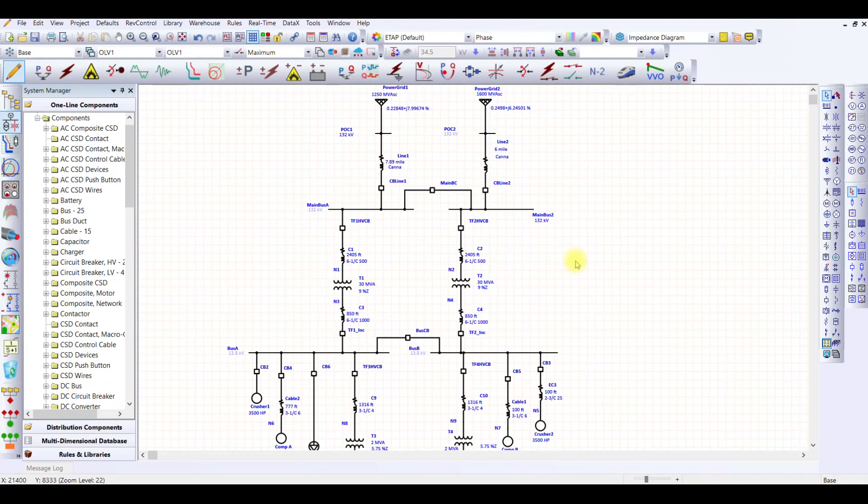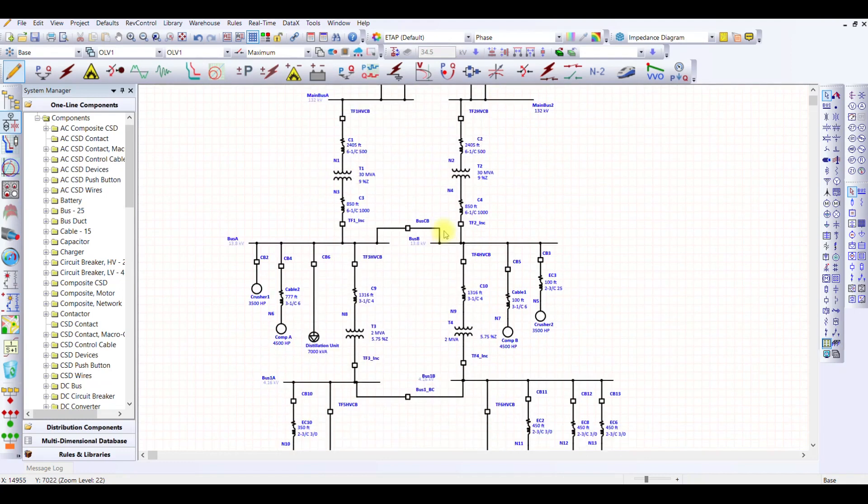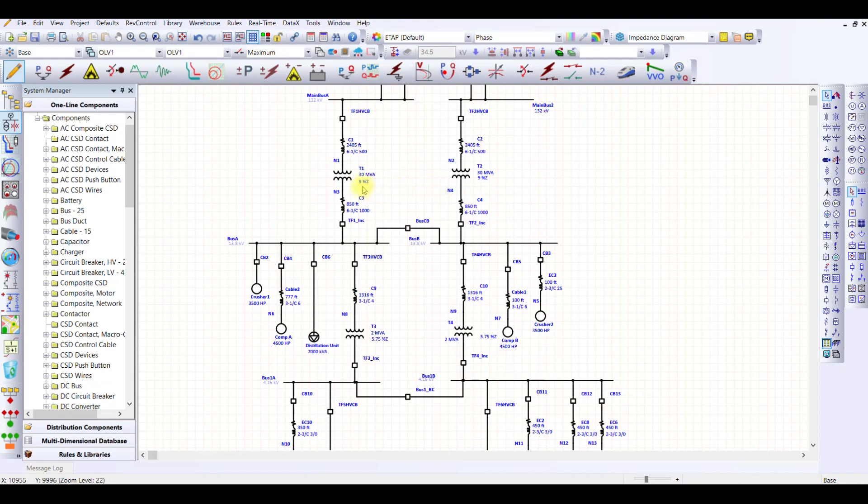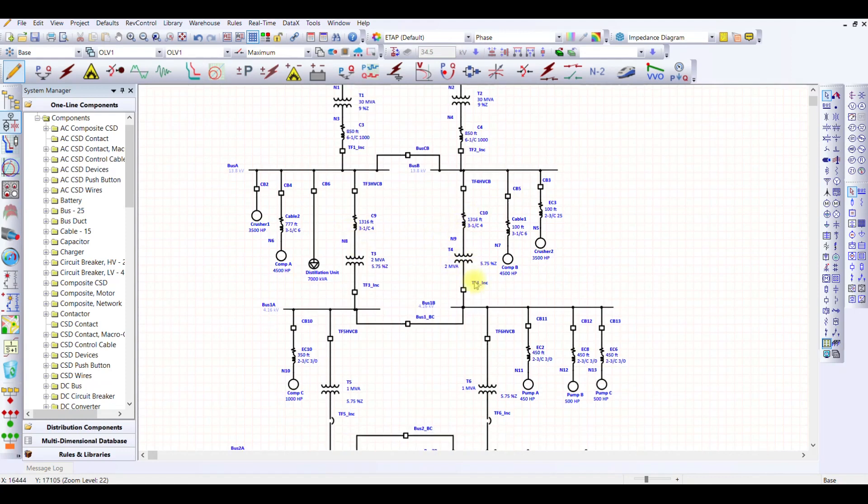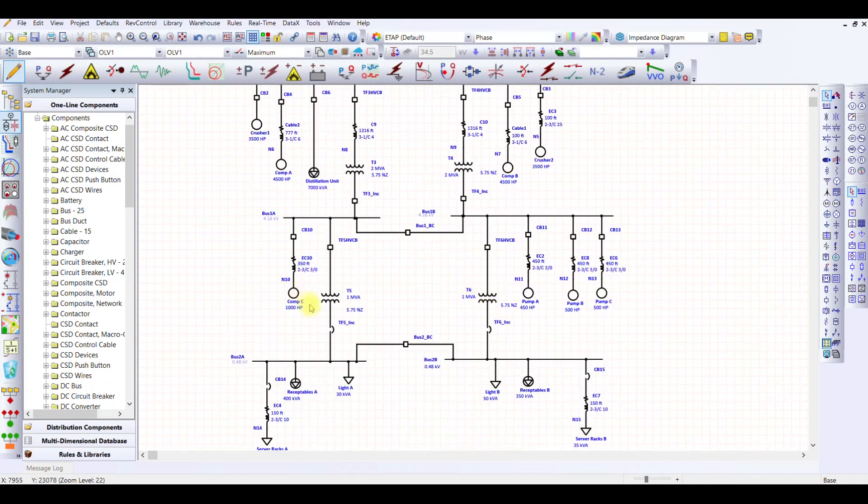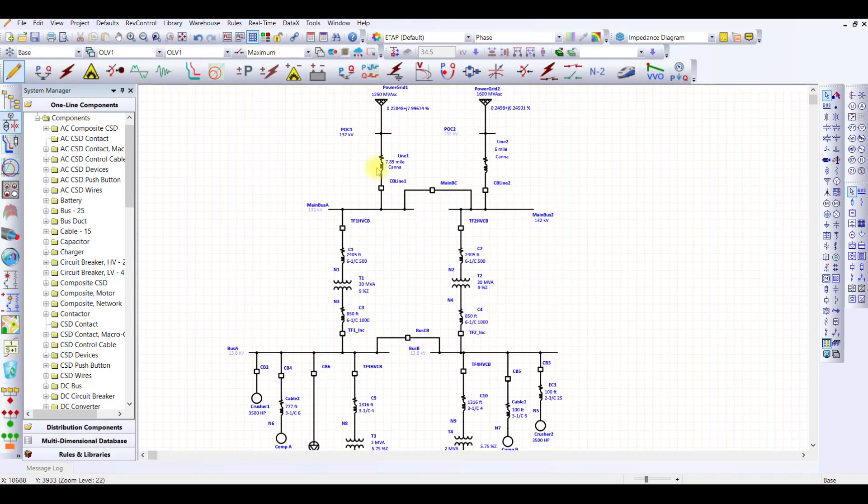One of the easiest ways to reduce the system impedance is to have multiple parallel paths. For instance, if we see here, we have two power grids. If these two are connected, the equivalent impedance will be much less. Similarly, these two transformers in parallel will have much less impedance. For instance, if the impedance is 9% here and 9% here, it means that the equivalent impedance will only be 4.5%, 9% divided by 2. So if we use this maximum configuration, it means that we are going to get the maximum fault current in this case.